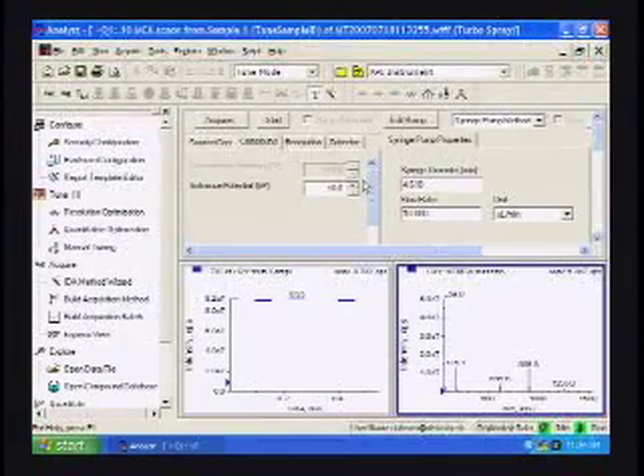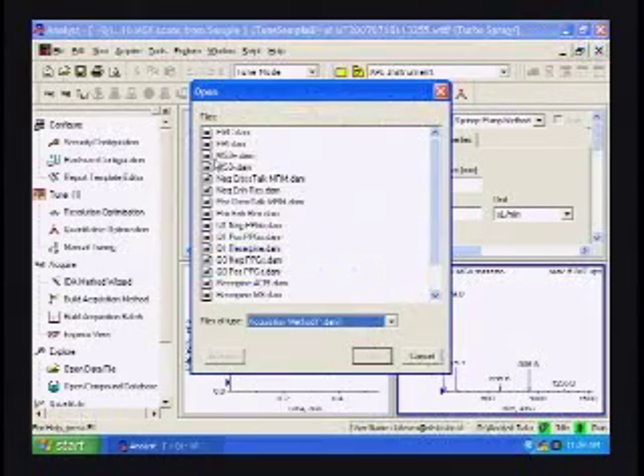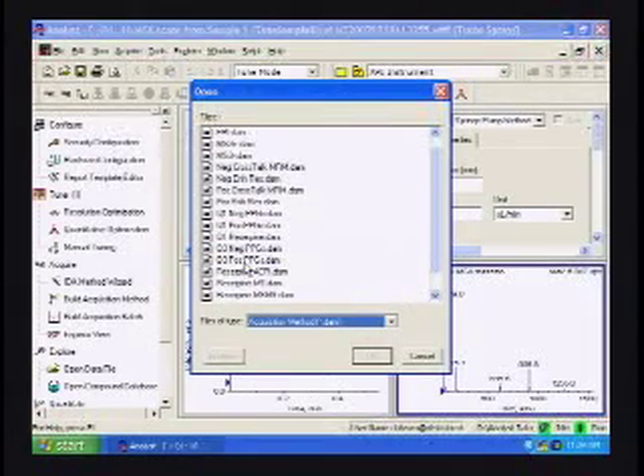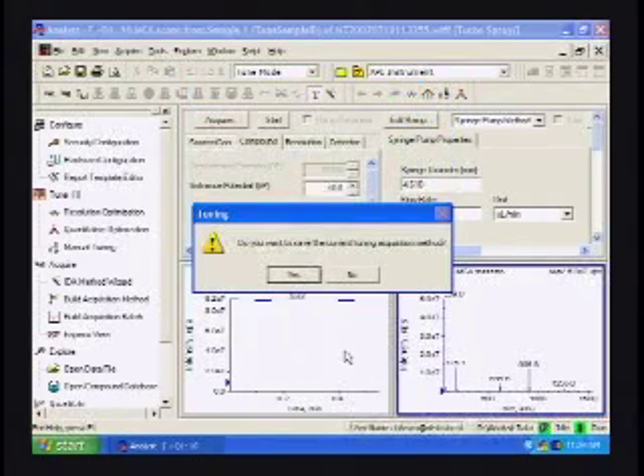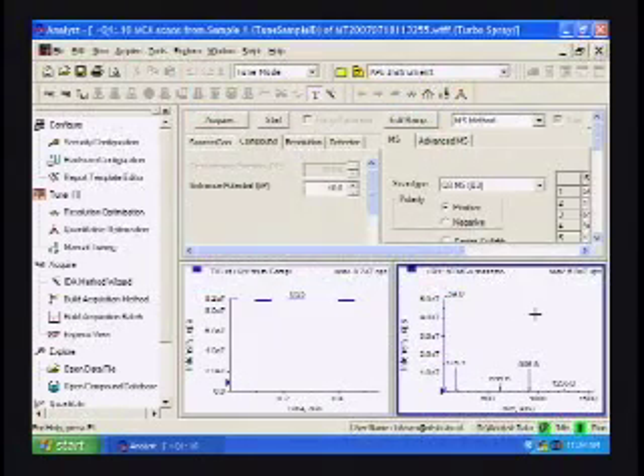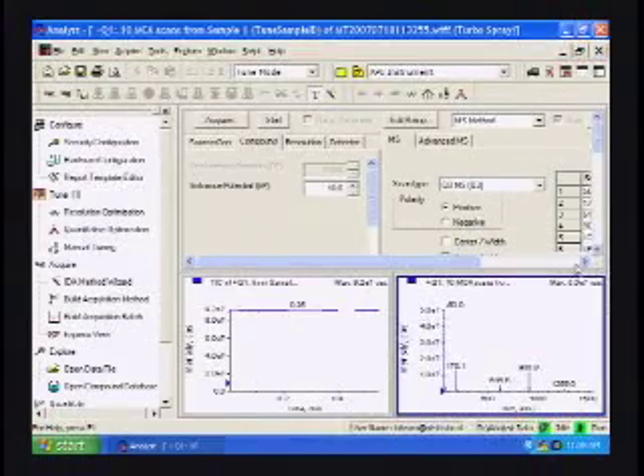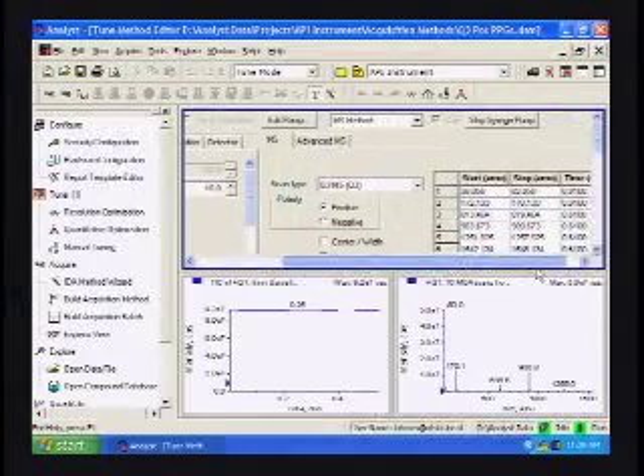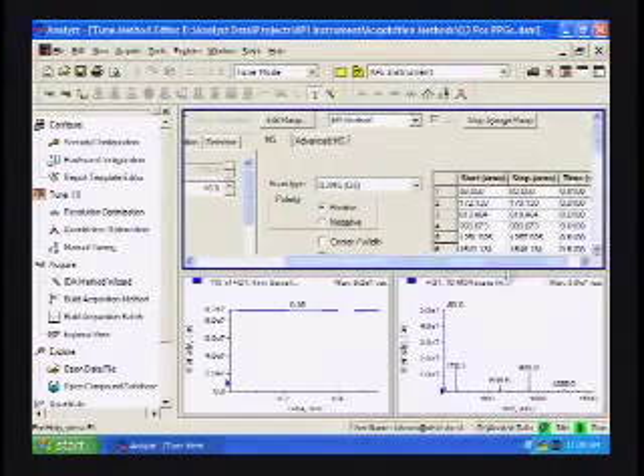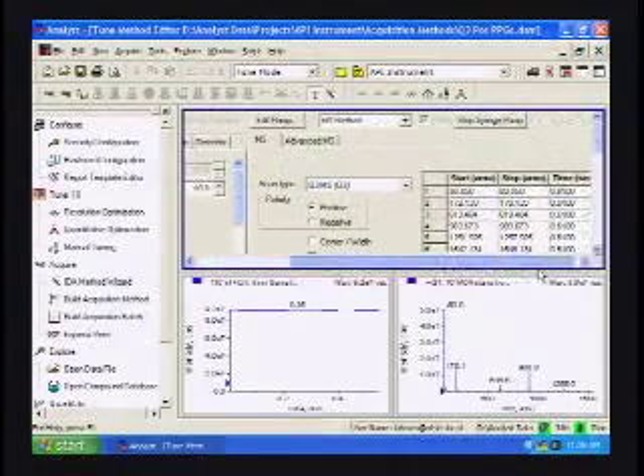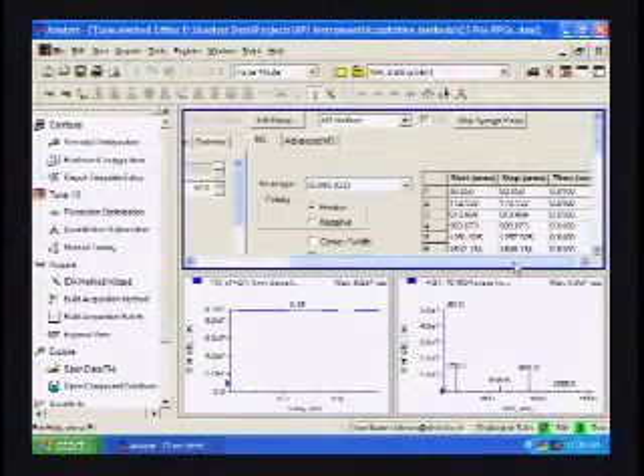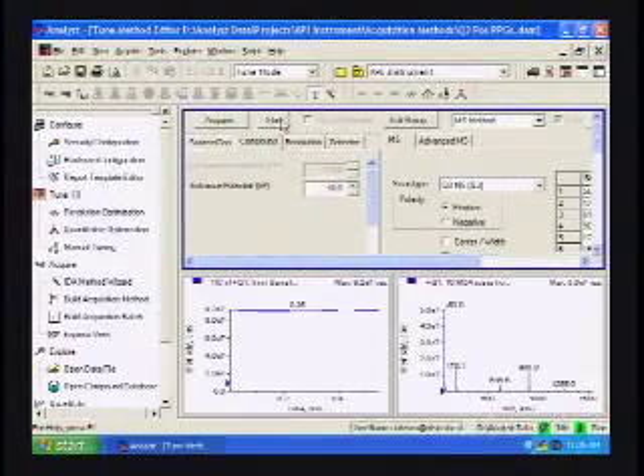Let's take a look at Q3. So in order to check the calibration of Q3, we need to bring up the Q3 positive PPG file. We do not want to save that other. Let's see, has it come up? Yes, it has, because here we see it's set for Q3. So again, the syringe pump is still running. And another important note on that is, so long as you're in the tune mode here, the syringe pump runs until you tell it to shut off. So let's go ahead and start the Q3 calibration check.